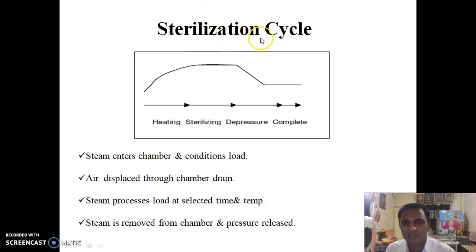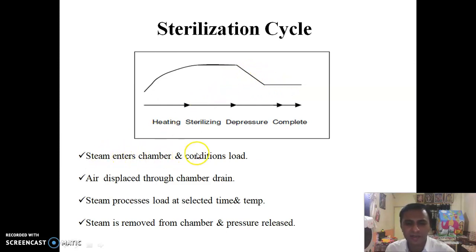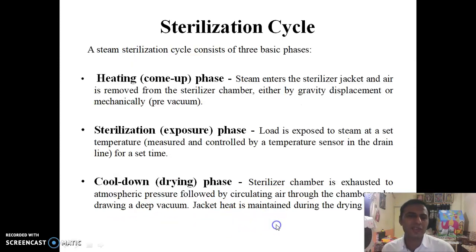The basic sterilization cycle consists of: first, heating takes place; then the main sterilization of material occurs; then depressurization and release of pressure complete the cycle. Steam enters the chamber, conditions the load, and air is displaced through the chamber drain. Steam processes the load at the selected time and temperature, then steam is removed from the chamber and pressure is released.